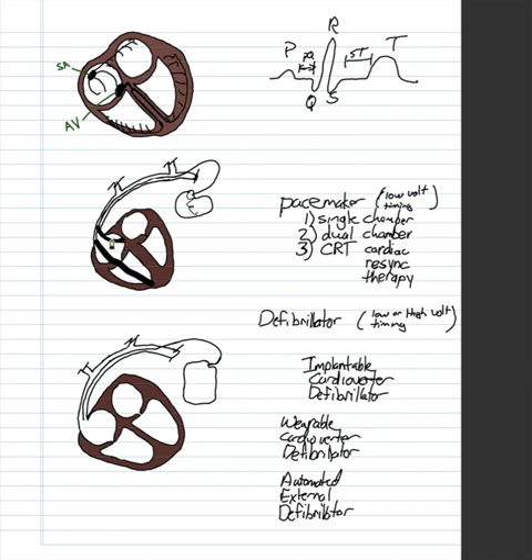And we can come in. So this one, if I can get into the atria here, I only need one side of the atria, and that's to start the P. So then I'll have two of these that are going to be able to start. So I have one wire that's coming down. So it's dual chamber. You can also, this is a single wire. This is two wire. So the two wires come off here. I'm not going to try to redraw that because that's really narrow. They split and come in, one to the atria, one to the ventricle. And that allows me to start P if after T has fired or after QRS has gone.